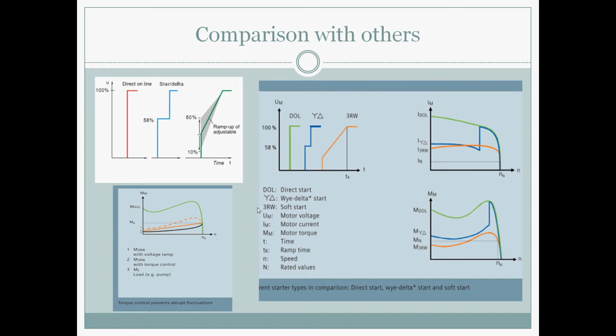Comparison with others. Here is a very brief comparison given for DOL, Star Delta, and our soft starter. You can see the direct online starter starts with a very huge amount. For Star Delta, there is a star connection given, and then a switching to Delta. What happens with the soft starter is that it starts at a rated value and then increases gradually. So there is no huge load on the electrical or mechanical side. The same thing happens with the torque control feature. The direct online starter has this amount of torque fluctuation, while the soft starter gives a very decent torque. That orange line is the soft starter one.